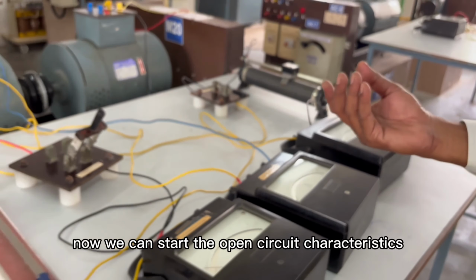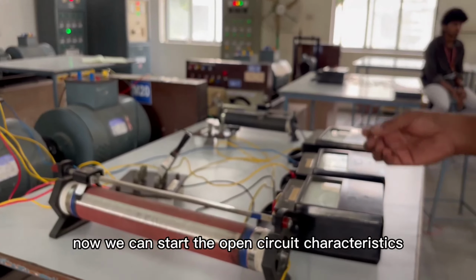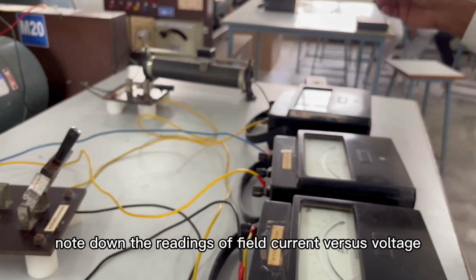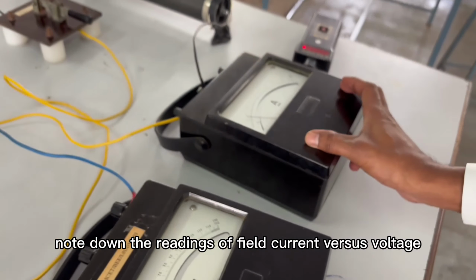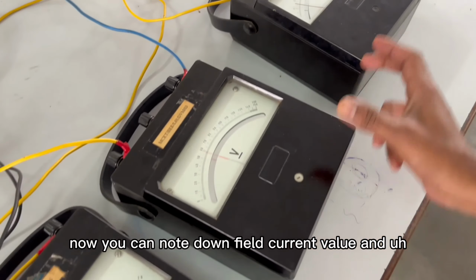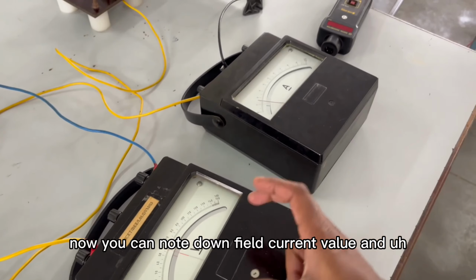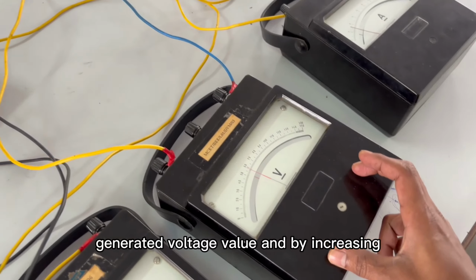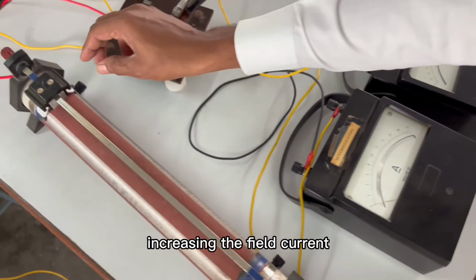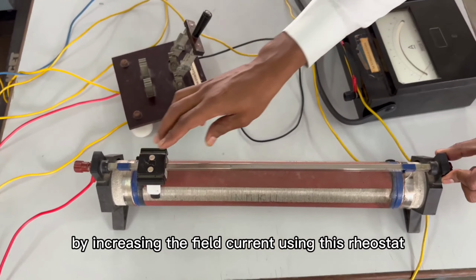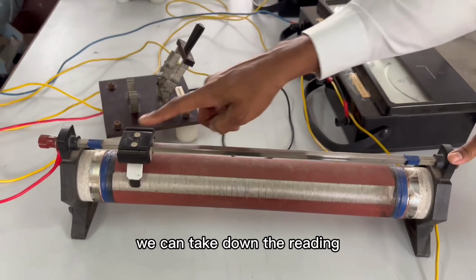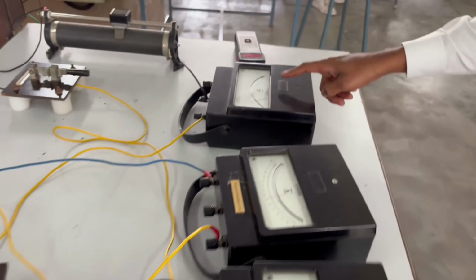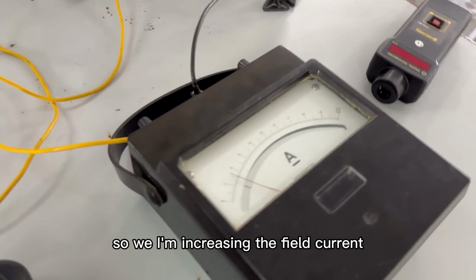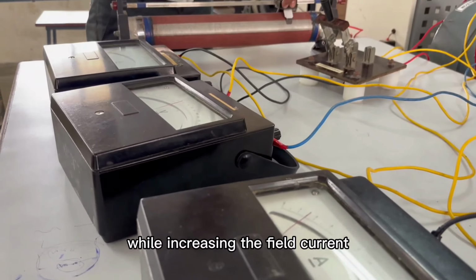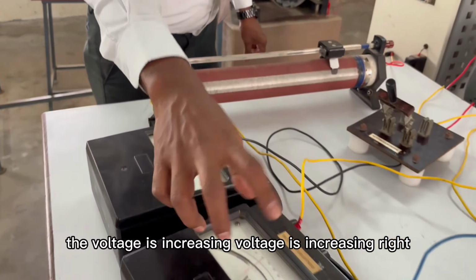And now we can start the open circuit characteristic. For the open circuit characteristic, note down the readings of field current versus voltage. Now you can note down the field current value and generated voltage value. By increasing the field current using this rheostat, you can take down the readings. So I am increasing the field current. While increasing the field current, the voltage is increasing, right?